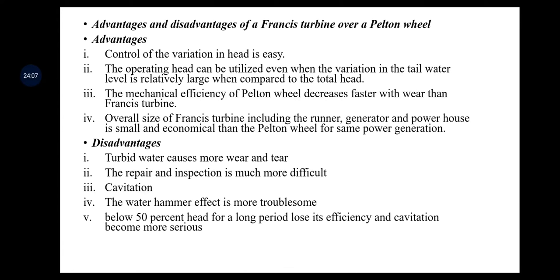Finally, below 50 percent of rated head — for example, if a Francis turbine works at 50 meters head and head drops to 25 meters — running it for a longer duration results in cavitation, which is a serious problem. This is not the case for the Pelton wheel: at lower head the work done is less, but the cavitation problem is absent.